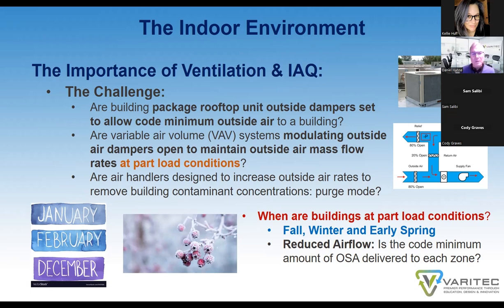Our variable air volume systems, VAV systems, modulate outdoor air dampers open to maintain outside air mass flow rates at part load conditions. When you're in your fall, winter, or spring, our loads decrease. Consequently, VAV boxes throttle back. So if you're to maintain the proper outside air within the occupied spaces, you have to increase the outside air percentage to the air provided to those spaces. The only way you can do that is the outside air damper serving an air handler must modulate open at part load conditions to maintain outside air levels. So the question is, are those modulating outside air dampers working appropriately?